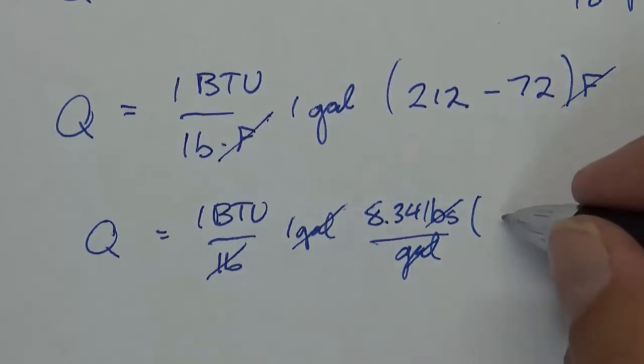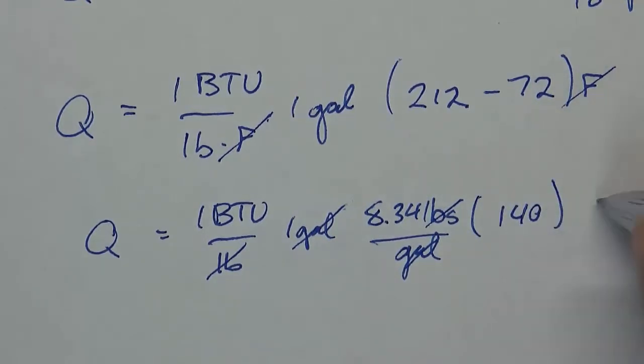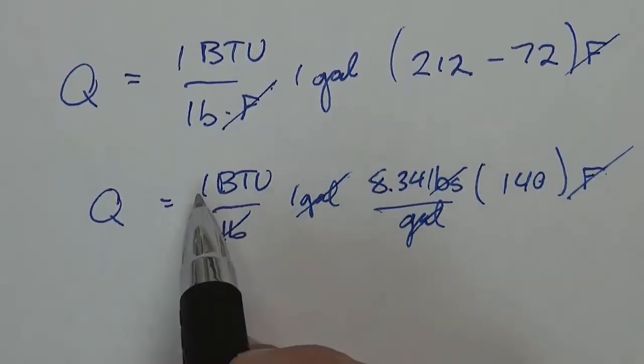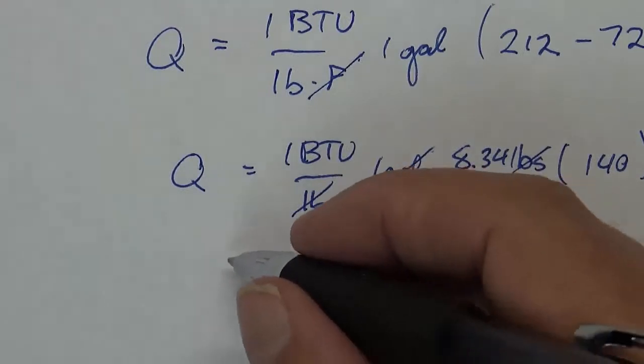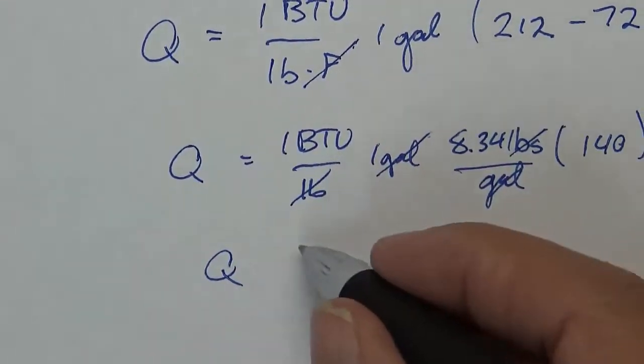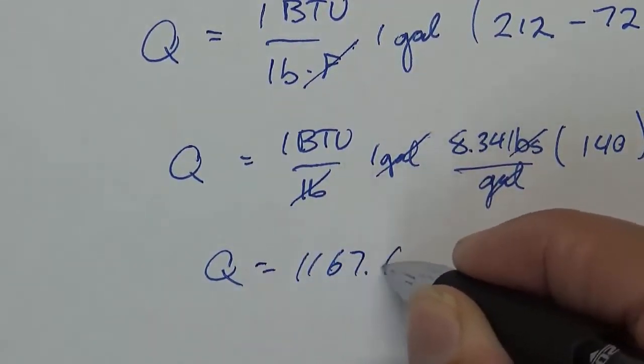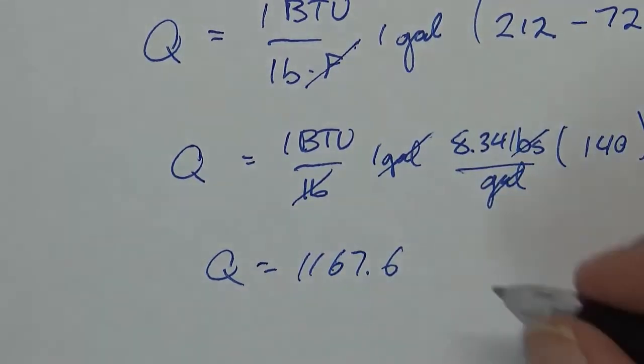I just still got to put in delta T, which is going to be equal to 140 F, and we already got rid of the F. So 1 times 8.34 times 140, that should give us our Q for answer number one, and I get 1167.6 BTU.